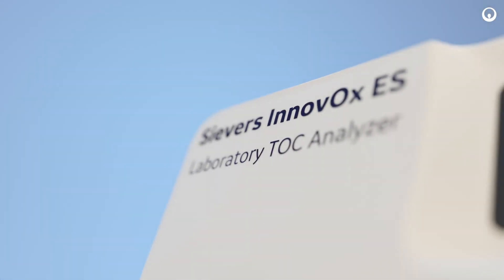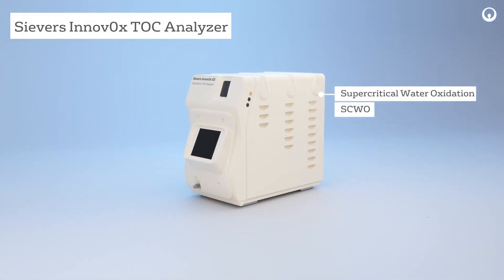As an alternative to combustion, the Sievers InnovOx TOC analyzer uses supercritical water oxidation, SCWO. This unique approach to wet chemical oxidation employs both heat and pressure. The increased pressure within the reaction cell dramatically improves the efficiency of the oxidation process, thereby offering better recovery for difficult matrices.